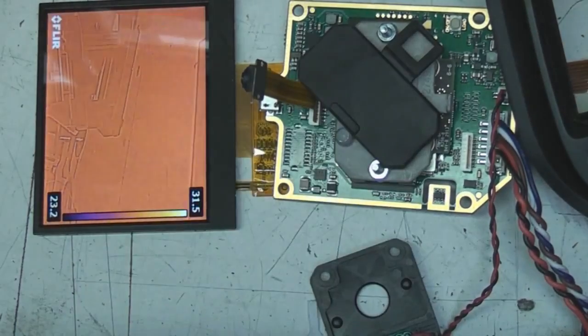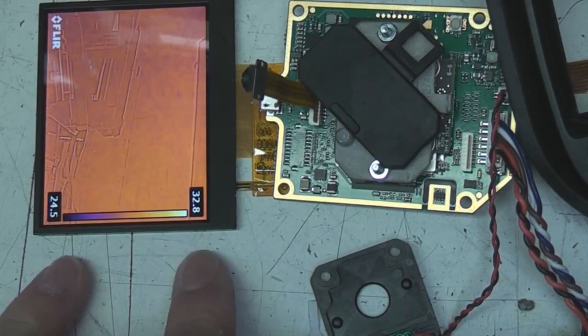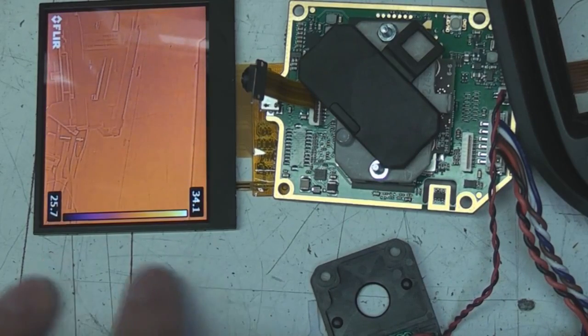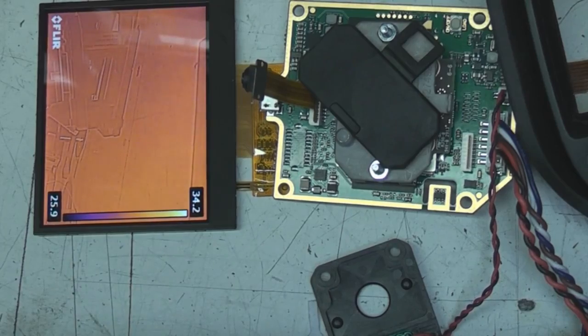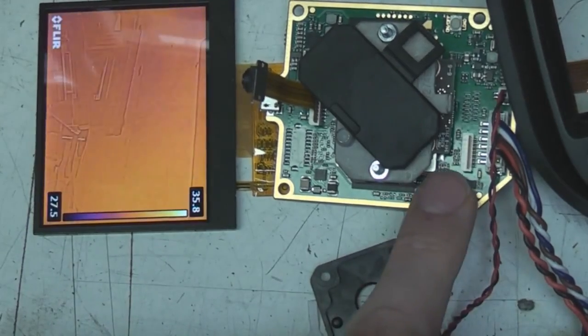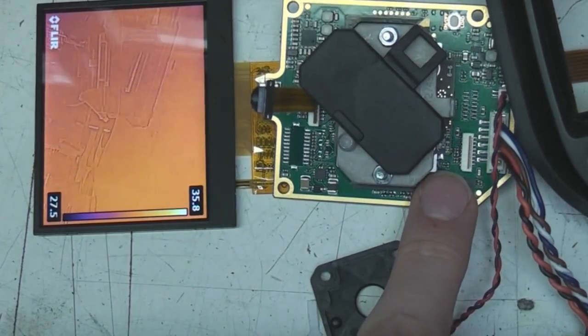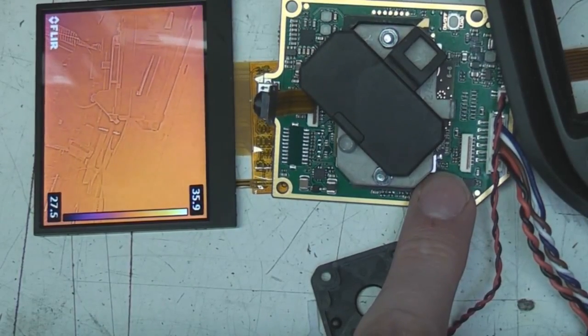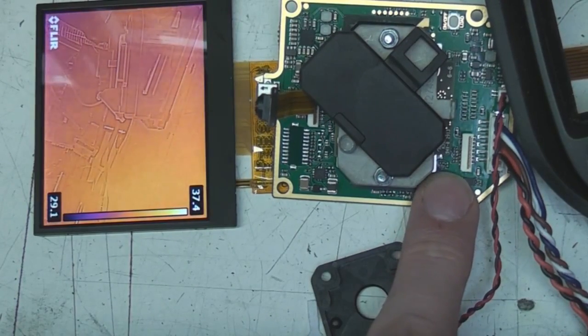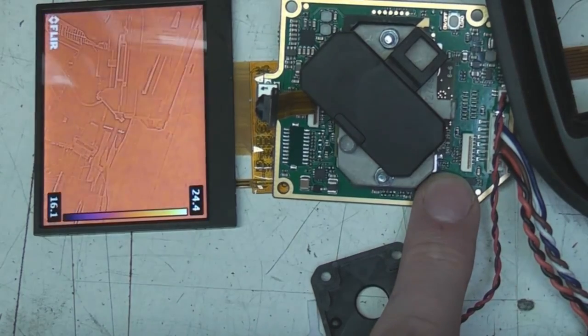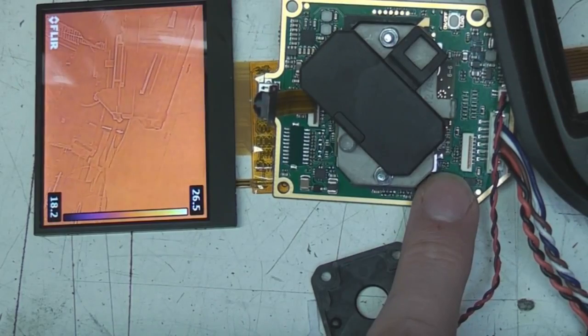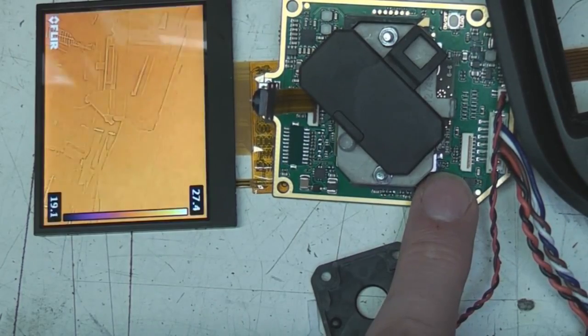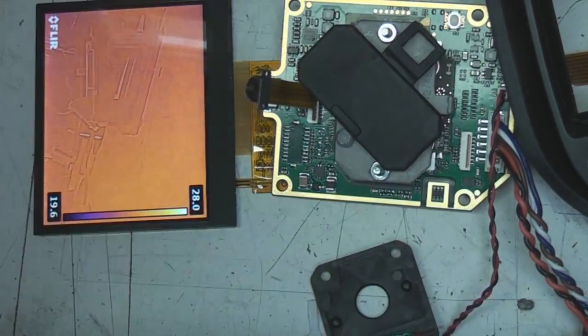This temperature sensor, I've just got this sat well. I'll put a cover over the lens so it sees a fairly flat background, and this is showing a temperature range between 25 and 34. If I warm this sensor up by sticking my finger on it, what we should see is that next time it does a calibration, those figures go down. Yeah, see, that's just suddenly dropped to 24 to 18, because the reference temperature is actually higher, so it's thinking what it's seeing through the sensor is lower.